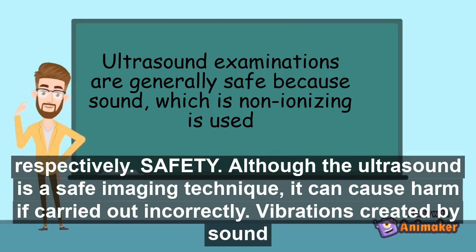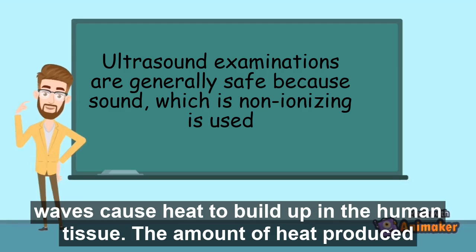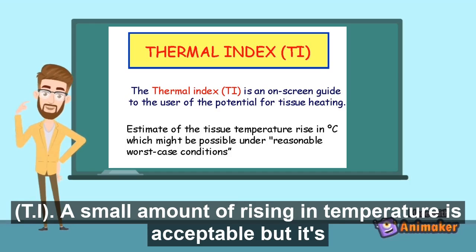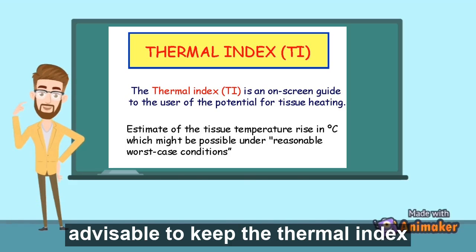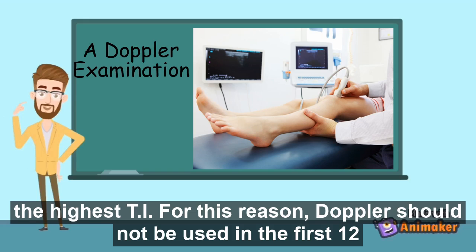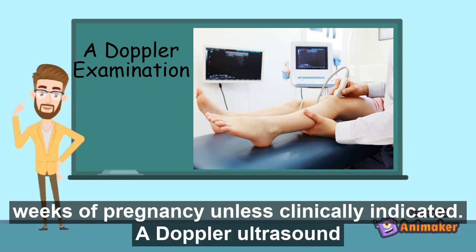Safety. Although ultrasound imaging is a safe and effective imaging technique, it can cause harm if carried out incorrectly. Vibrations created by sound waves cause heat to build up in human tissue. The amount of heat produced is calculated by the ultrasound machine and is called the thermal index. A small rise in temperature is acceptable, but it is advisable to keep the thermal index below 1 at all times. Doppler sonography uses a pulse signal which creates high amounts of heat and has the highest thermal index. For this reason, Doppler should not be used in the first 12 weeks of pregnancy unless clinically indicated.